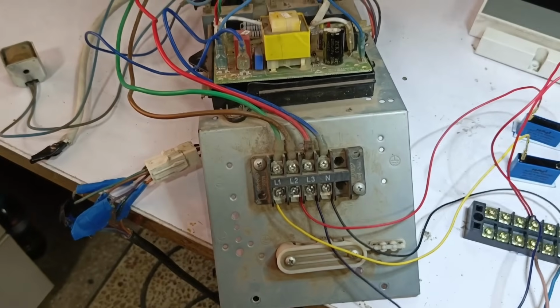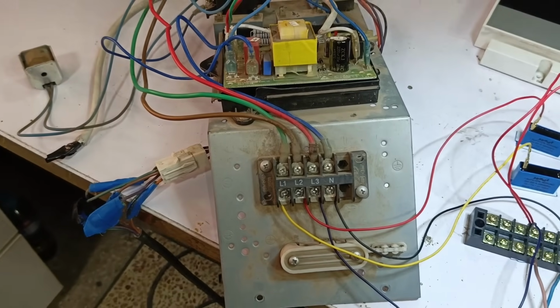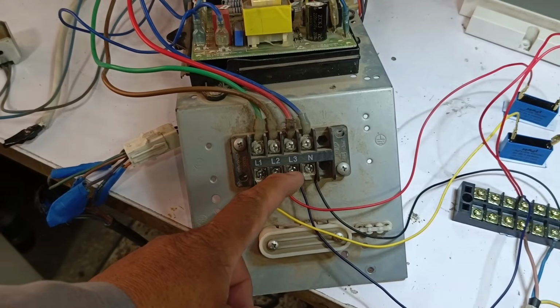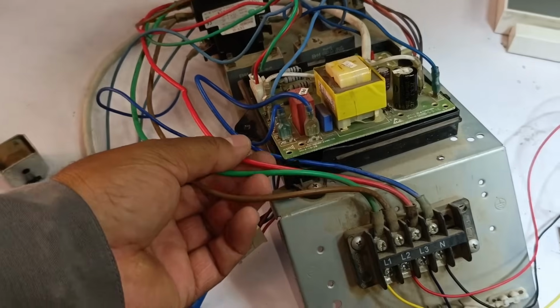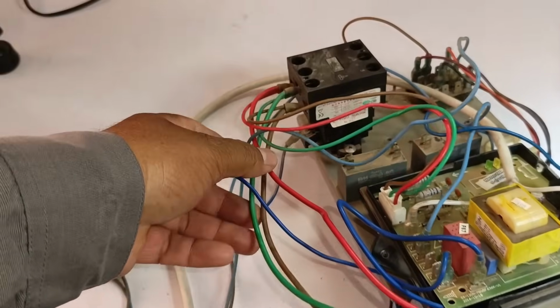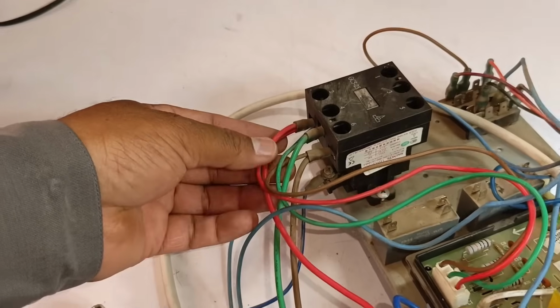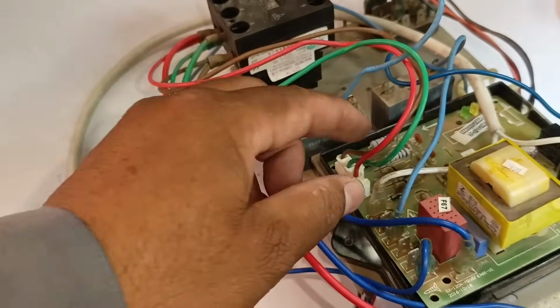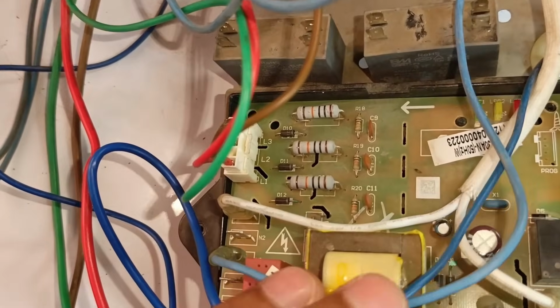Now, I will properly show you how this sequence is working. Now you can see that the connections for line 1, line 2, line 3, and neutral have been given. All 3 supplies are entering directly into the connector. These 3 wires are again coming into the connector where the phase detection circuit is installed. A small mistake happened. I should have shown the testing first and explained the connections afterward. But since I have already completed the connections, we will now proceed with testing to check whether the phases are actually present or not.